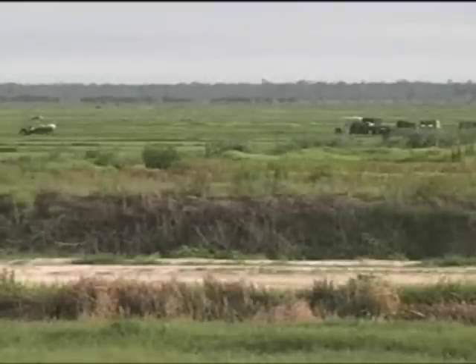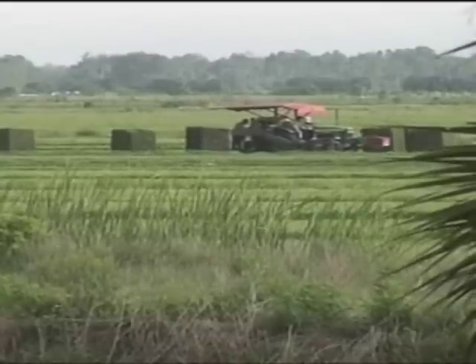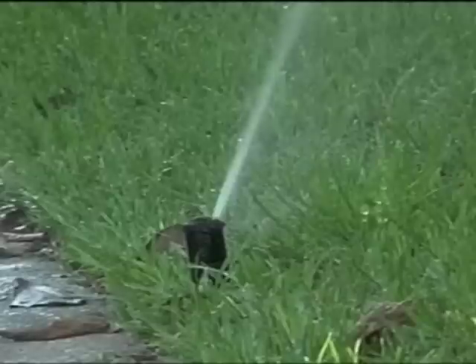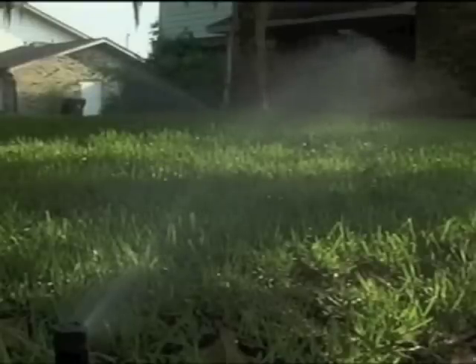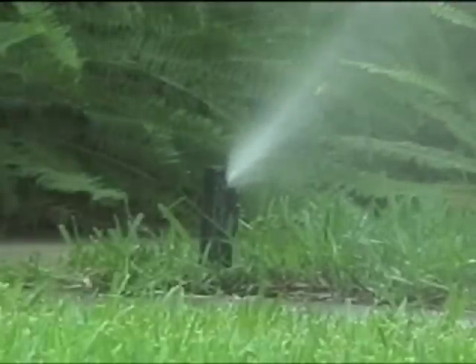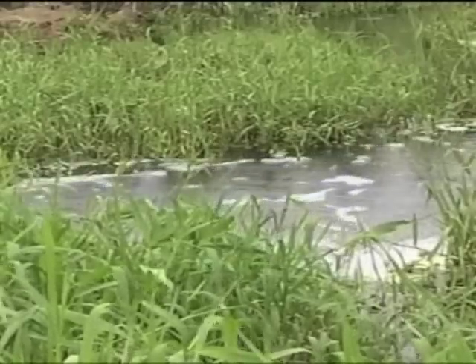The facility was constructed to treat 3 million gallons per day of wastewater. This reclaimed water was sent to a 2,000-acre sod farm. However, by 1995 it became apparent that the sod farm couldn't accept all of the reuse water, so the excess water was sent to three golf courses and several subdivisions. This solution was good for the dry season, however not for the wet season. So as a solution, the county sought to get a permit to discharge during the wet weather into the St. Johns River via the Four Mile Canal.